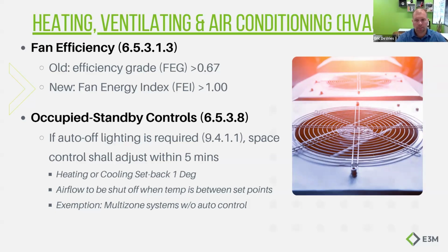I think the last kind of change before we talk about some functional performance testing requirements for HVAC is occupied standby controls. I try not to bring my opinion too much into educational seminars, but if I was one of the 8 advisory council members, I was trying to die on the hill of this not having this as a requirement, but the decision was made to adopt the book as written. So in multi-zone systems, like a VAV system or a VRF system, automatic off controls need to be present. So your lighting occupancy sensor has to connect to your VAV box and set the room temperature back by a minimum of 1 degree, and it has to look at the airflow requirements.